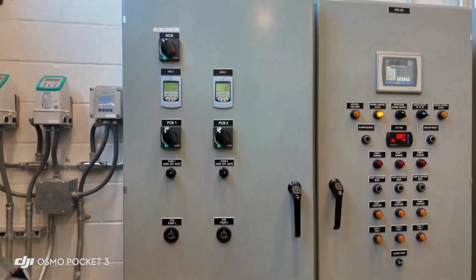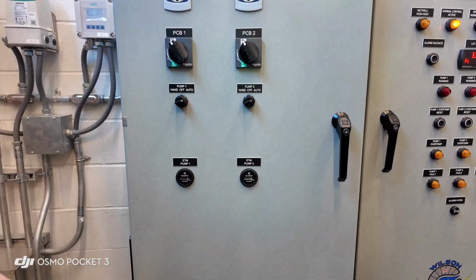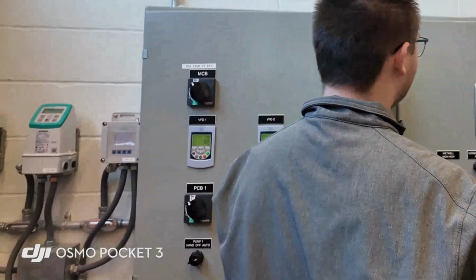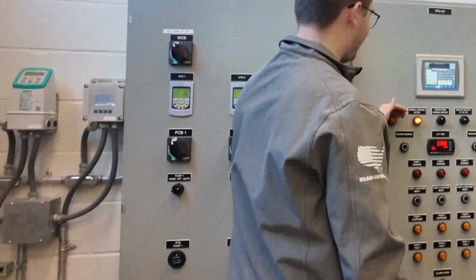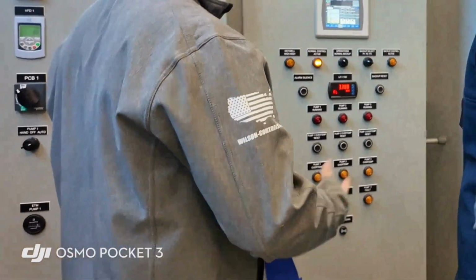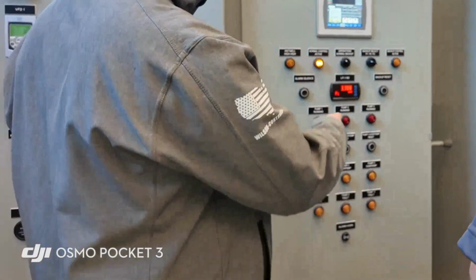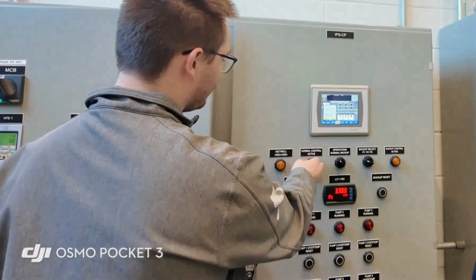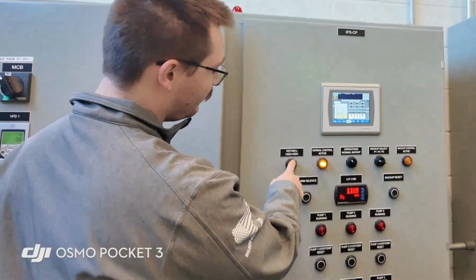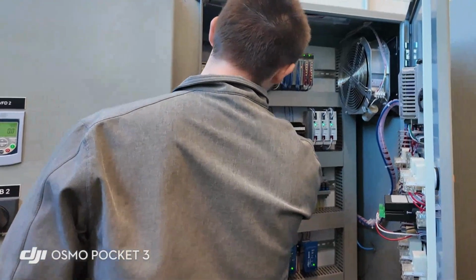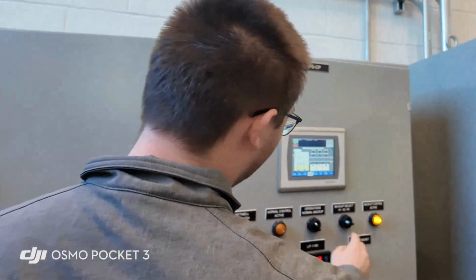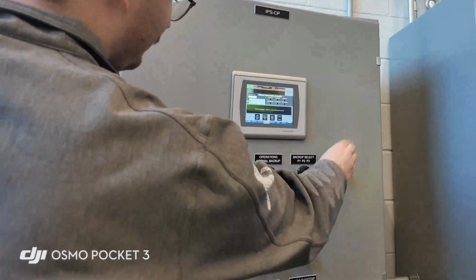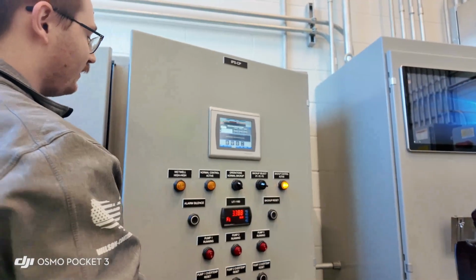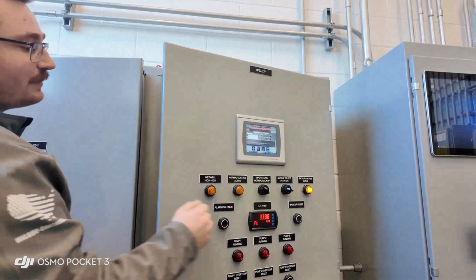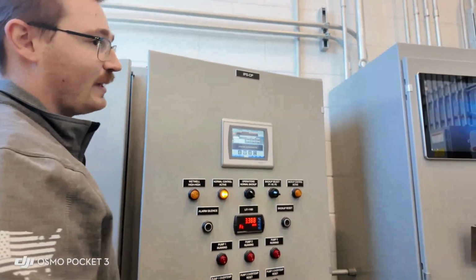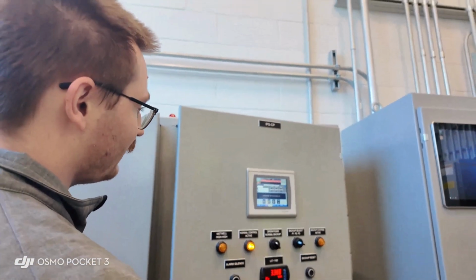Down here we have manual pump runtime counters, and we also have them displayed on the OITs too. We start with the indicating lights for the high level. So there's a float inside the wet well. If it reaches high level, it's going to enter backup. In normal operations, it's going to tell you that it's normal. If you get a high level, or a simulated high level, the high level float activates the relay here and it's going to switch from normal to backup. If it goes back to normal and everything's good, it's going to keep it in backup until you manually reset it. And then it's going to go back to 4 to 20 control from the PLC.